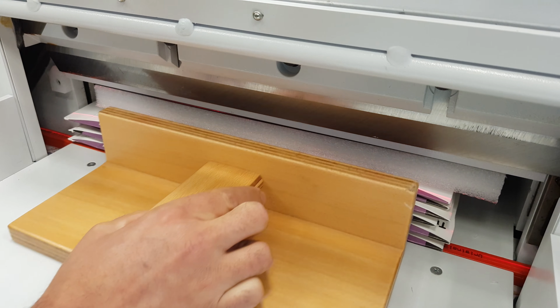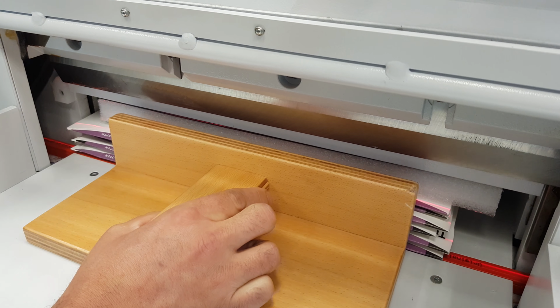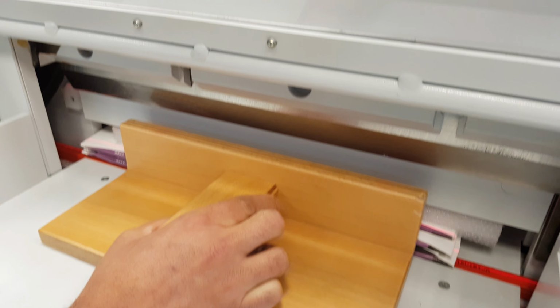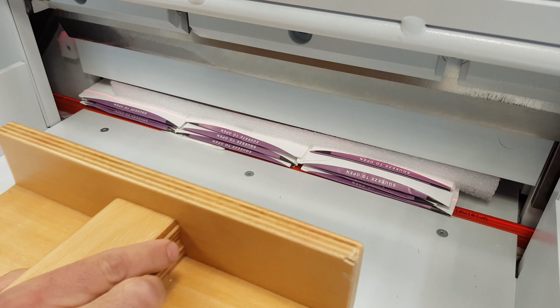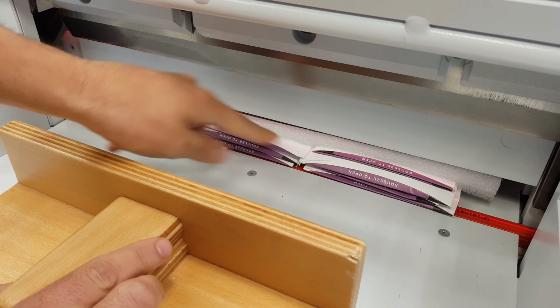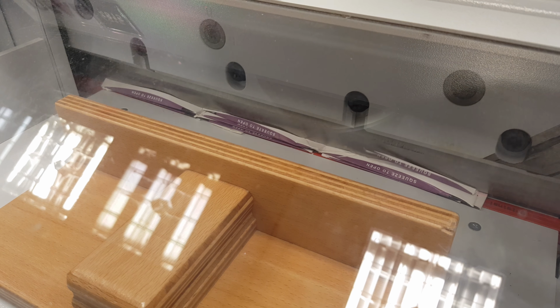and then we can use our tapper to push them all to the back plate. Once you push it to the back plate, we wind down our clamp, and we can wind it down quite tight because we've got the insulation on the back plate that we've fabricated for the machine. So it squishes them all down, but it's not going to harm your samples as well. So once we close the lid, we can cut this lot up.